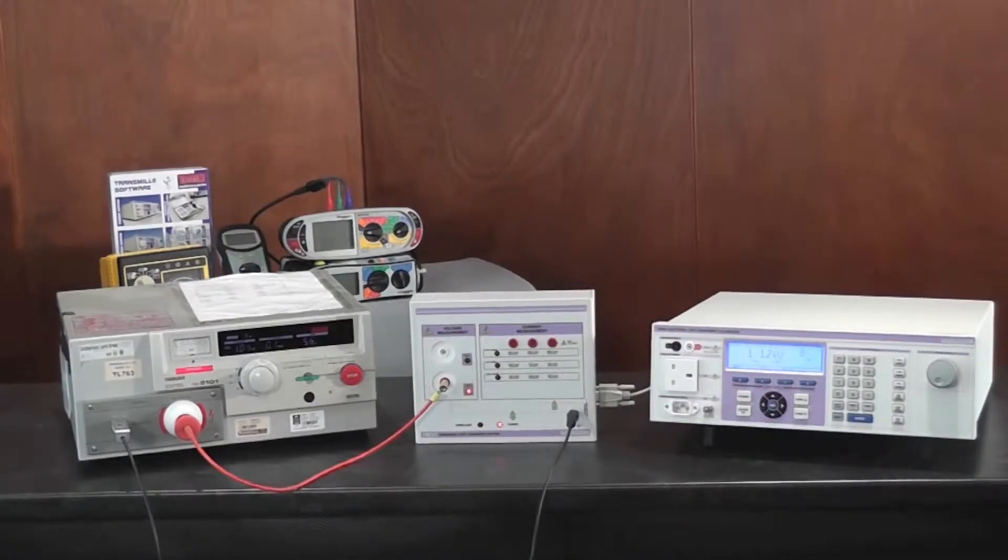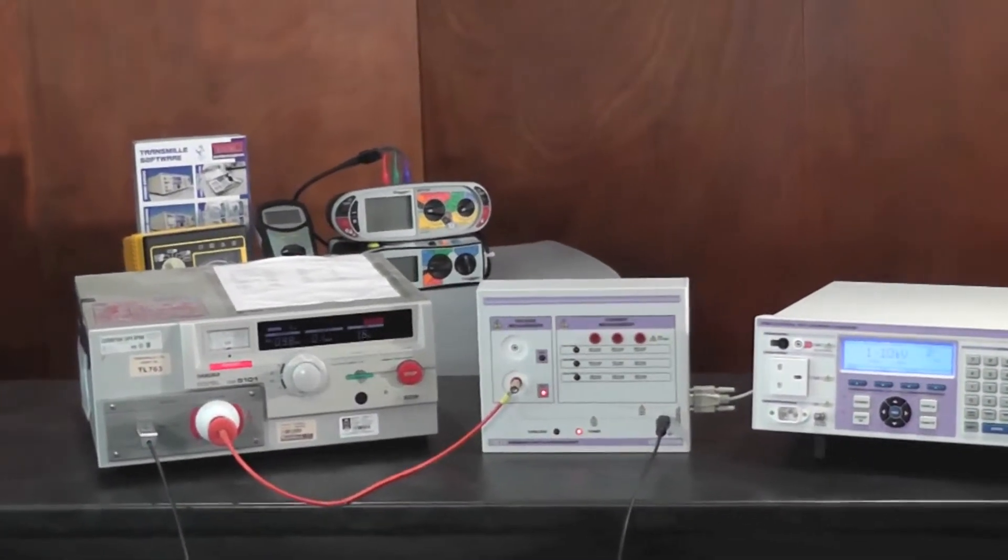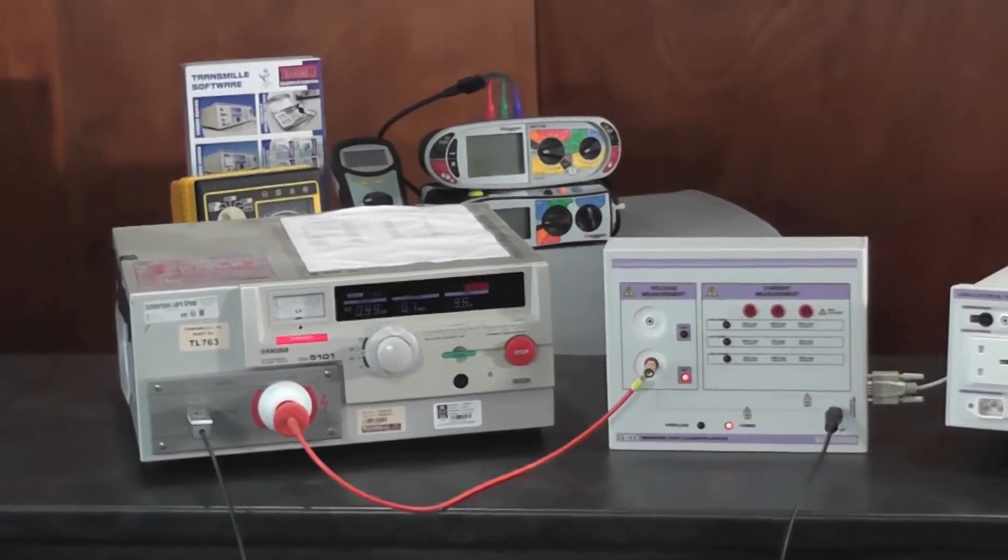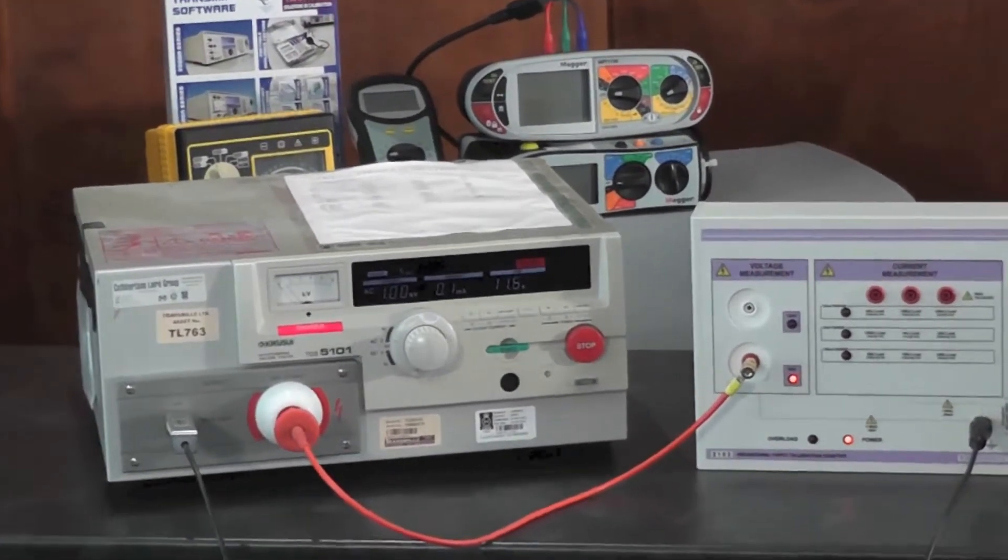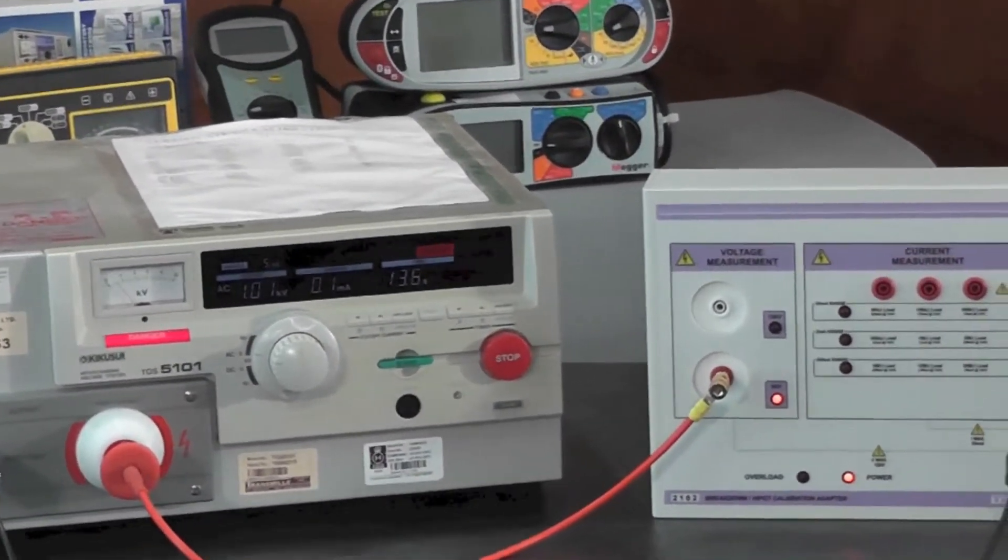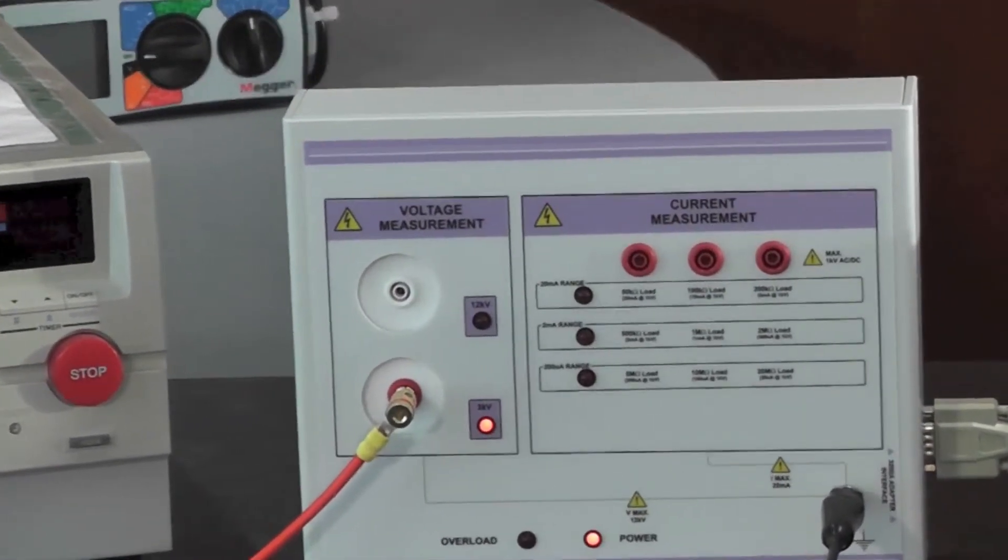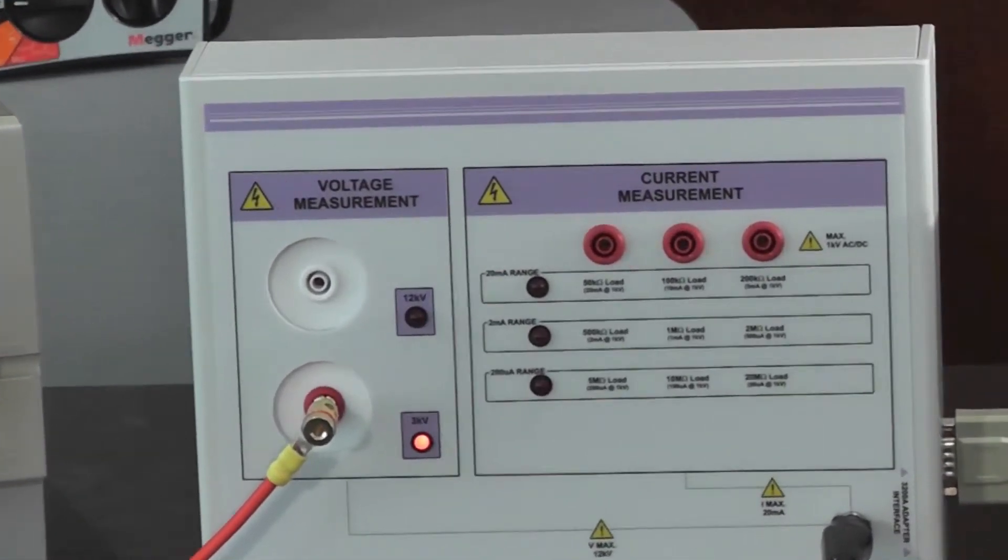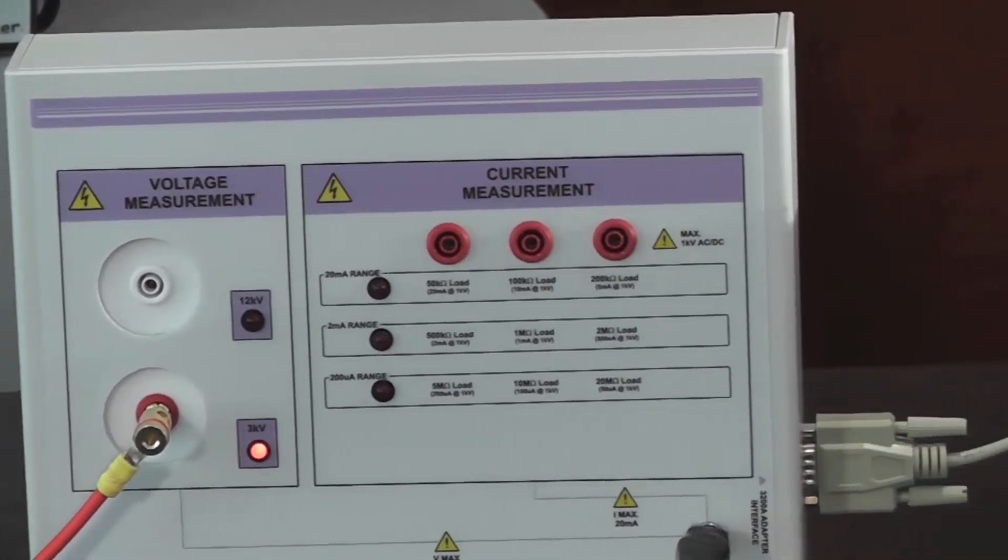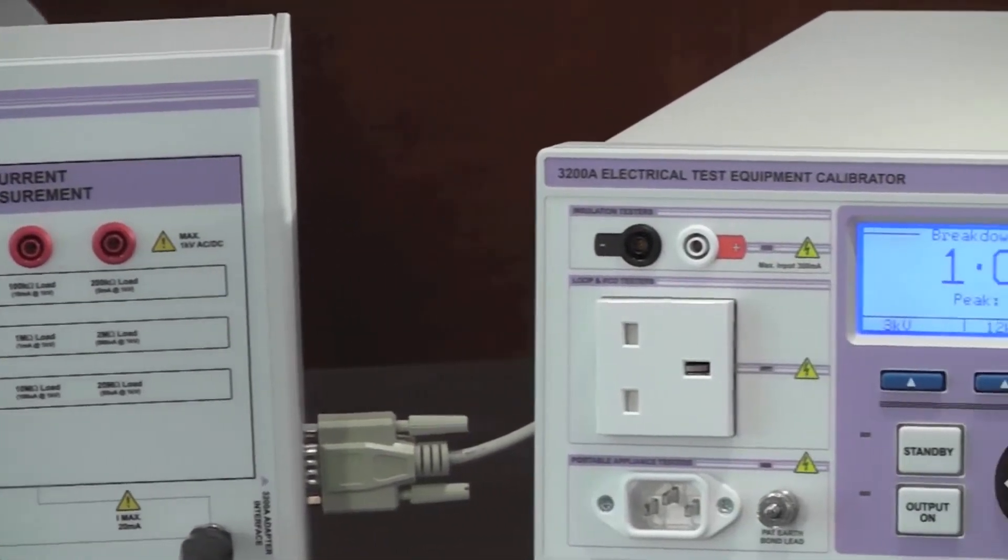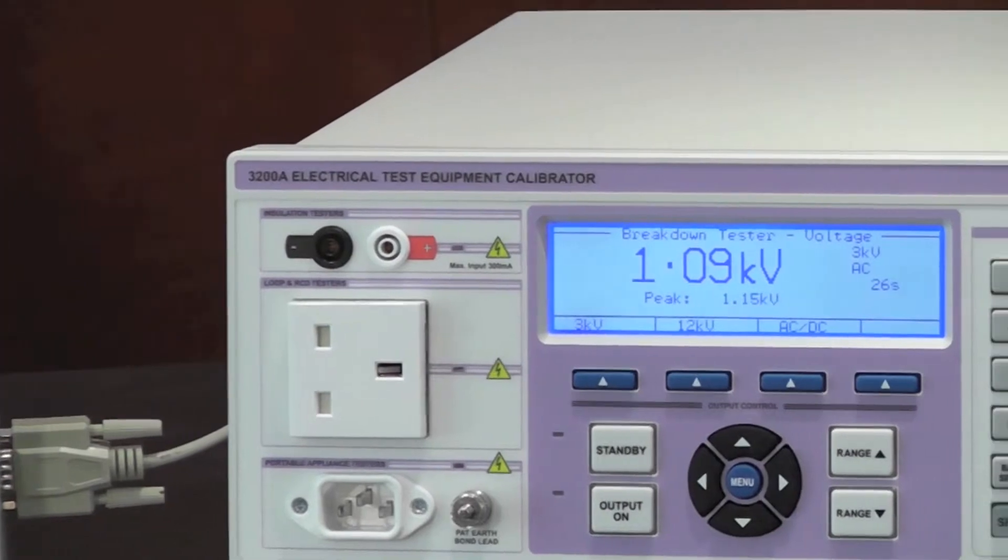The 3200A provides a unique solution for calibration of breakdown and high pot test adapters using the external breakdown adapter. Using the external adapter, voltages of up to 12 kV AC can be measured with loading of up to 20 milliamps. This makes calibrating these dangerous instruments safe.